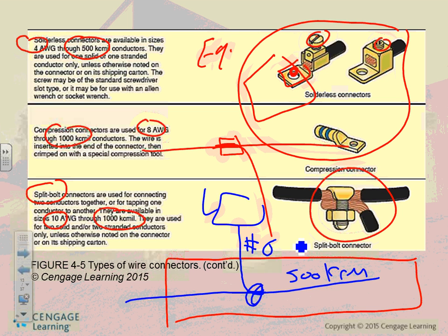Aluminum cover? Yep. Guys, you know, when you design and install a system, safety has a 4-leg stool, like I always say. Number 1 is the equipment has to be safe. You listed equipment. You can't make an unsafe equipment installed and designed safely. So equipment has to be listed, which I'm sure it is. That's number 1. Safe equipment, listed. Number 2, design safe. So when you design, you take all these rules into consideration and design it safe. Number 3, the 3rd leg, install safe. When you send those electricians there, torque it, install it safe to specification. Anybody remember the last one that everybody forgets?